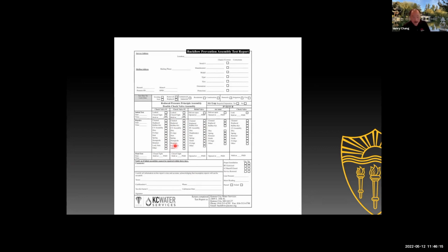You can see also it asks the tester to identify if the installation is proper. Also asks if the relief valve is exercised, okay? One of the things we mentioned earlier is to try to get that relief valve opening point the first time it opens, not after it's exercised. Sometimes, accidentally, the relief valve could be exercised. So the administrative authority wants to know that. Okay, was that relief valve exercised? Some other areas have said, hey, an exercising of the relief valve could be a repair. We don't consider it a repair, but some areas do. So they may want to know that, okay?